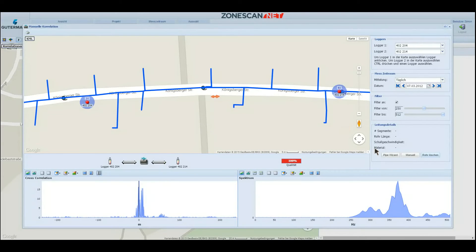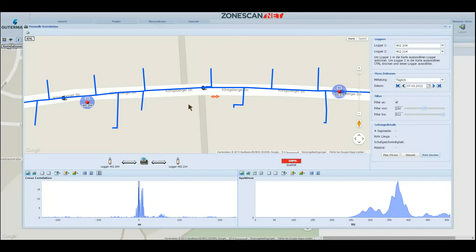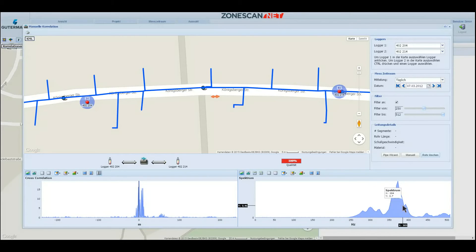I will now delete the old data so we can see the interface as it is, without any inputs. At this point the system does not know the properties of the pipe, such as the material and the diameter, nor does it know the route of the pipe and therefore the length of it. All the system knows is that the two loggers are picking up the same noise, and that this noise is in a frequency band typical for a leak. We are now starting the Pipe Wizard.